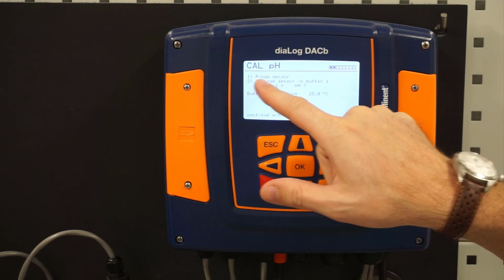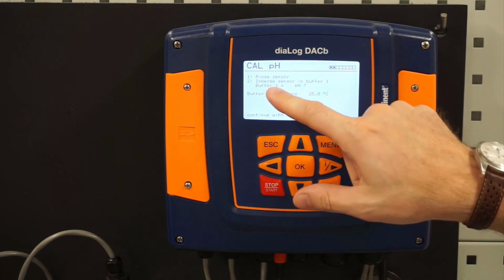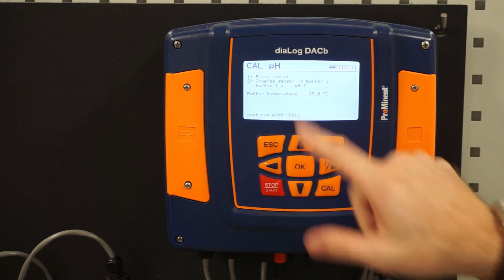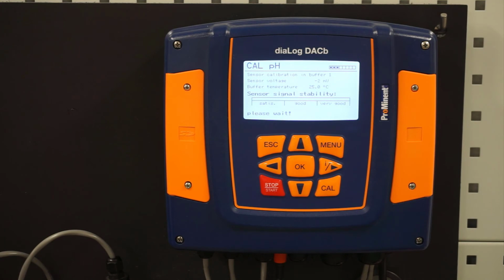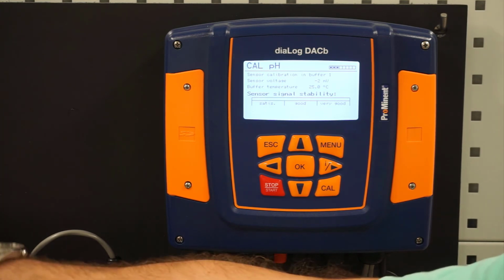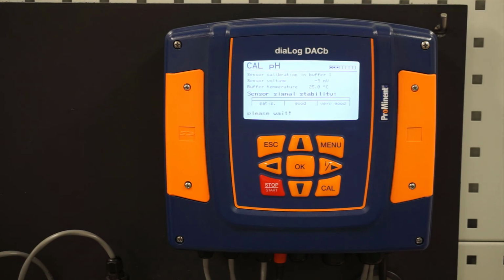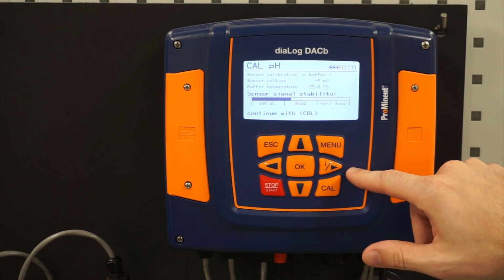So at this point we would take the sensor out, we would rinse it, and then we're going to stick it in our buffer of 7. Once we have that going, we're going to hit calibrate, and then we're going to look for our signal to stabilize, and it should only take a couple of seconds for that to happen. In this case we're using a pH simulator to simulate our signal in, so you'll see it should be very stable, depending on how our battery is in our simulator. So now you've seen our sensor has come in, the signal's stable here.